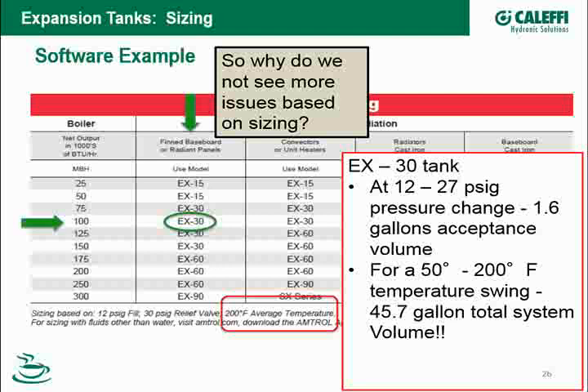Yeah, and the other thing with the compression tanks, the first thing everybody recognizes when they go from a pre-pressurized expansion tank to a compression tank is the size increase on the tank. But the second thing that has to also be recognized as an added cost on installation is that I have to support that tank, and that tank's going to be at least half full of water. So you have a lot of weight that you're supporting somewhere in the building, whether you're building some sort of saddle for it or trying to support from the joist of the floor above. Good point. Yeah.